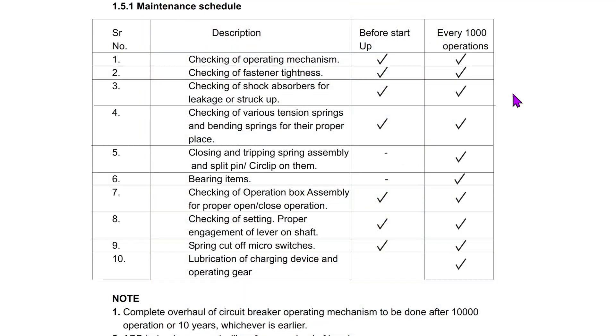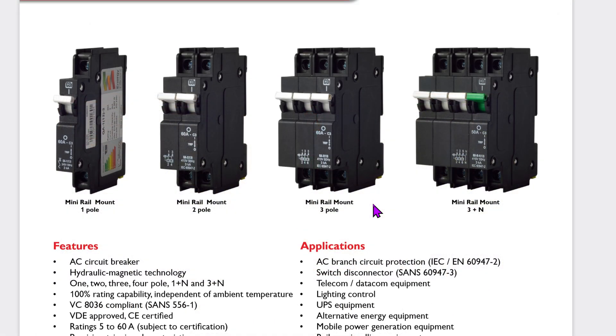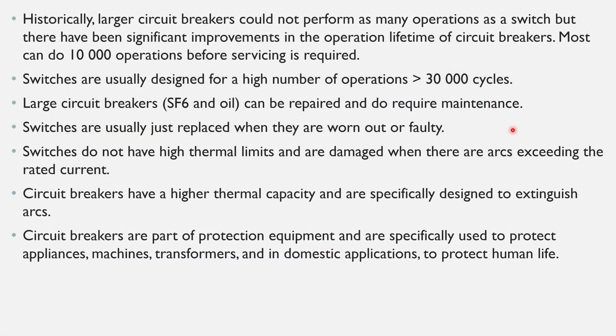Larger circuit breakers are designed to be maintained — the manual will explain what to do after a certain number of operations. Smaller circuit breakers are not designed to be opened at all and should be replaced when faulty. Switches too are usually just replaced when they are worn out or faulty.